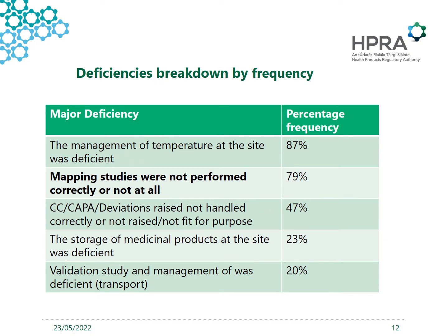For mapping studies that were not performed correctly or at all: not at all is self-explanatory, but examples of mapping studies not performed correctly, we've seen acceptance criteria not documented, and studies not being conducted in line with the protocol. A huge amount of effort is put into the protocol and then the actual study is not conducted in line with said protocol. The alarm limits or the set point of the room was not documented, or things like the environmental temperature on the day was not documented. So the company failed to create that snapshot in time to show what the conditions were at the time of the study.